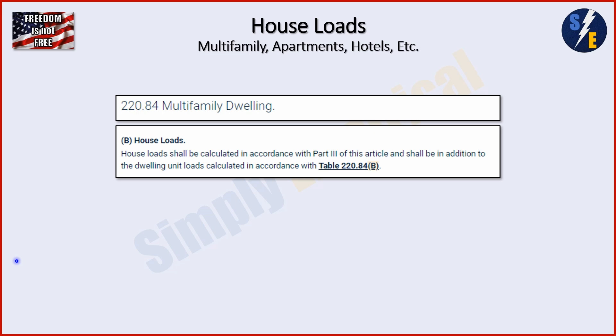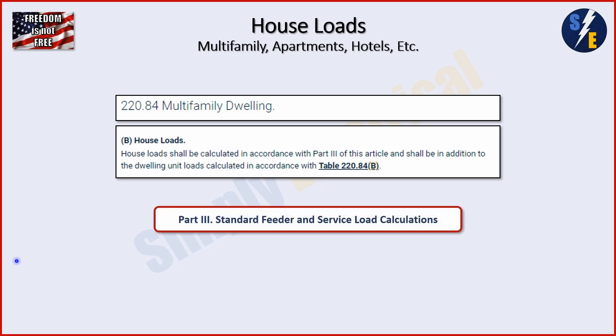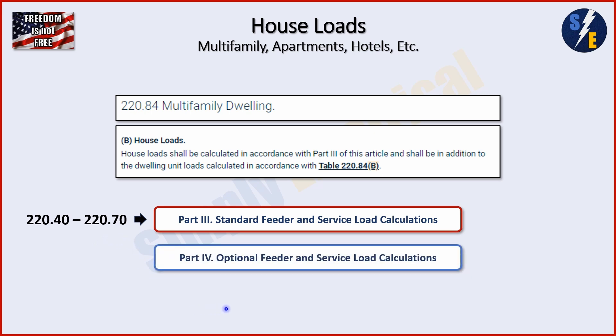We're under 220.84, which is the optional method in article 220, but it's referring us back to part three, which is the standard method for our calculation when we add these house loads. As a quick recap on how the code book is laid out: part three is for standard feeder and service load calculations, found in 220.40 through 220.70. Part four is the optional feeder and service load calculations, found between 220.80 and 220.88. So 220.84 puts us smack dab in the middle of part four — the optional method — but it's telling us we have to go back to part three for the house loads specifically.